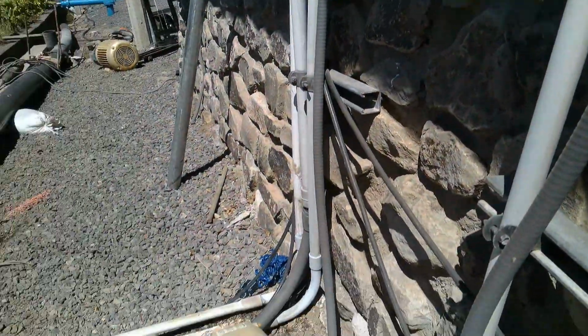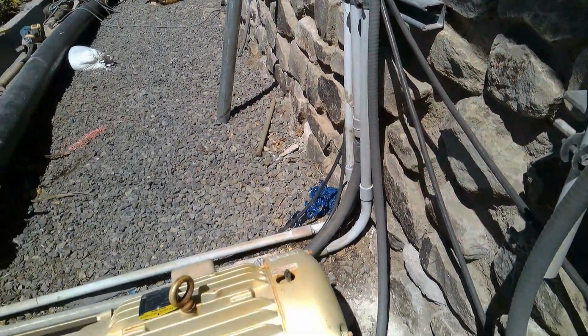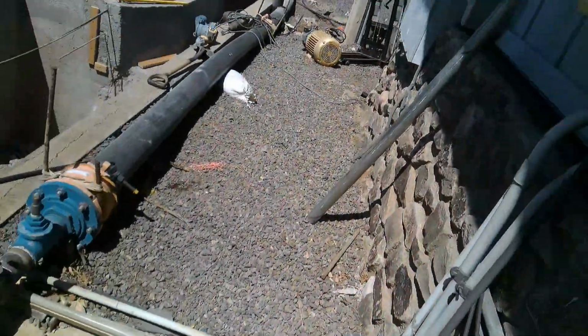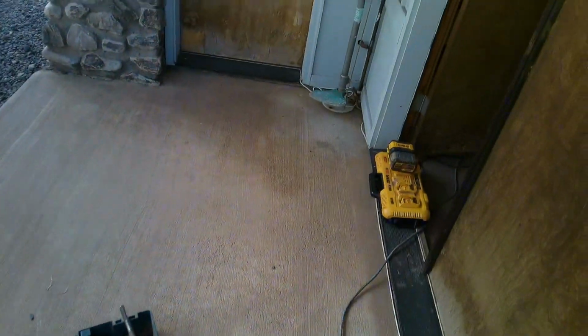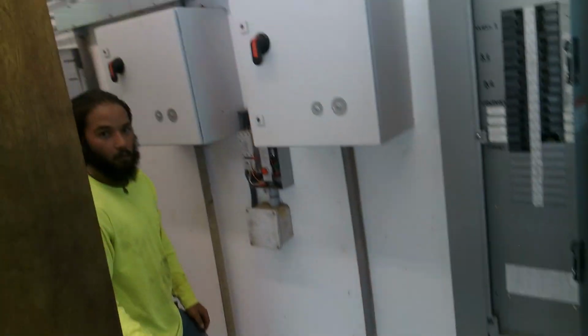Okay, so the breaker's on. Wait till I'm in position. So we want it to spin that way. Okay, ready? It is spinning that way. It's spinning the wrong direction. Okay, so it's spinning the wrong direction. So I could either take apart those splices out there, shut off power, or just change 2 of these.